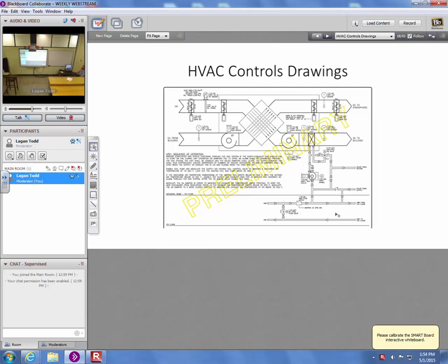In the commercial world, where there's a specific temperature controls contractor who's hired to do the building-wide controls installation, they might be creating these drawings custom to the control system that they're installing over the top of some other people's equipment. Right? So some manufacturer made the air handler that was purchased and installed on site, and that air handler was shipped without any controls, versus when you buy a residential furnace, it comes with all its controls.